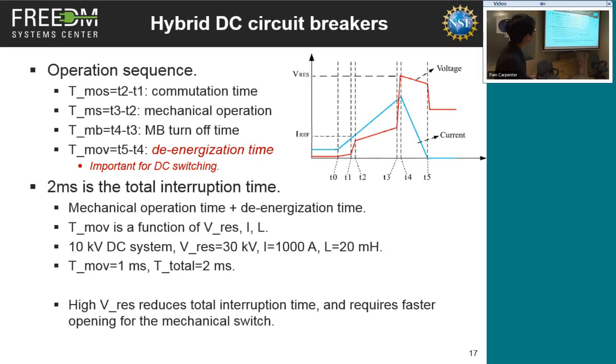After that, the current will flow into the MOV. The MOV clamps the voltage, and this clamped voltage is sometimes called the residual voltage of the MOV. That voltage will try to bring the line current down to 0 to finish the rest of the job. I have named each of the time periods. First, the commutation time, then the mechanical operation time, and the main breaker turn-off time. There will be a de-energizing time, which is the time the MOV works.